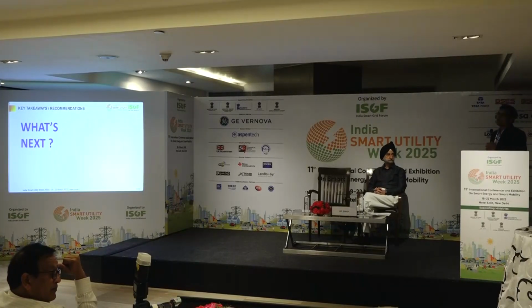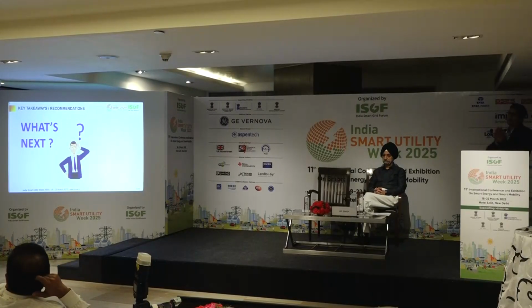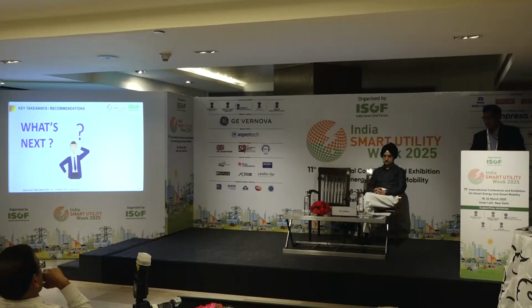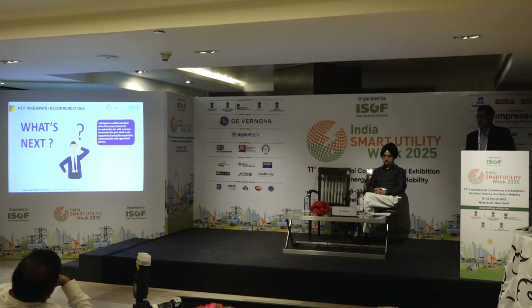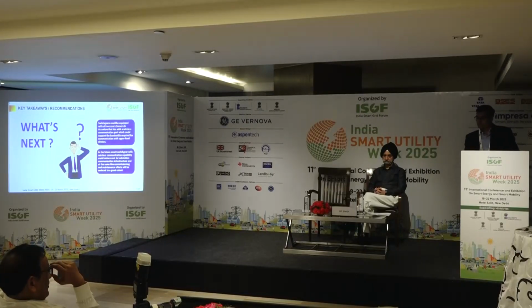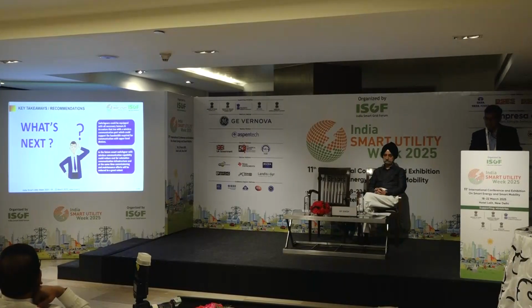Now, where are we heading to? Gradual improvement is there. What will be the development, what will be the end to this substation automation system? You might have many views, but my view is that switchgear could be equipped with all necessary sensors and actuators, with one wireless communication port which could support the bandwidth requirement for communication with upper level devices. In the future, smart switchgear with wireless communication capability could reduce the cost of substation communication infrastructure, and at the same time commissioning and maintenance effort will be reduced to a great extent.